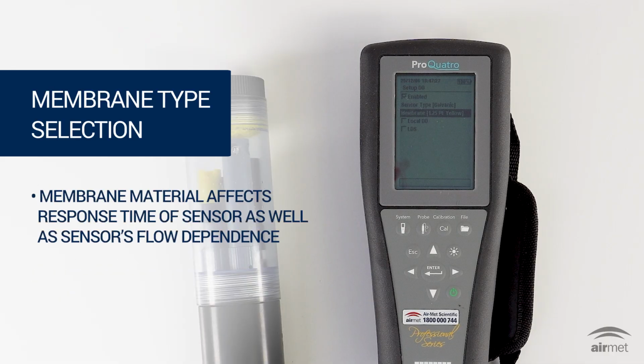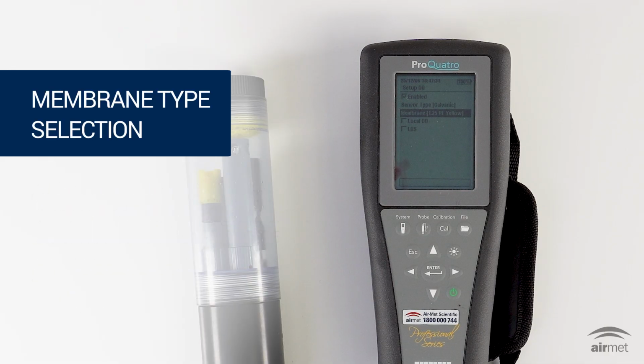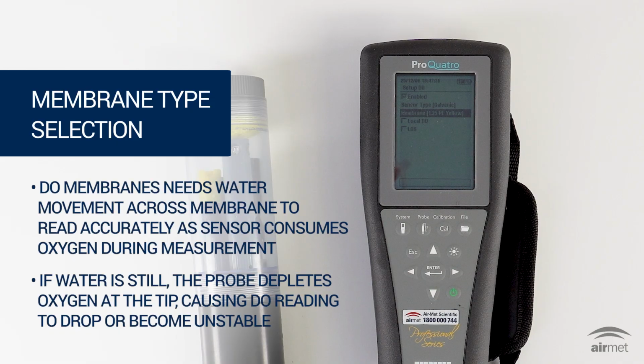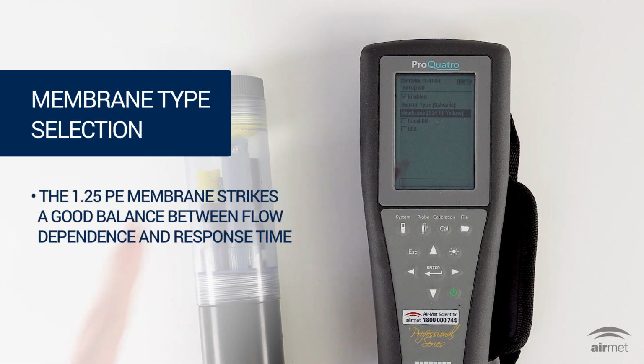The membrane material affects the response time of the sensor as well as the sensor's flow dependence. A DO membrane needs water movement across the membrane to read accurately as the sensor consumes oxygen during measurement. If the water is still, the probe depletes oxygen at the tip, causing DO readings to drop or become unstable. The 1.25 PE membrane strikes a good balance between flow dependence and sensor response time.